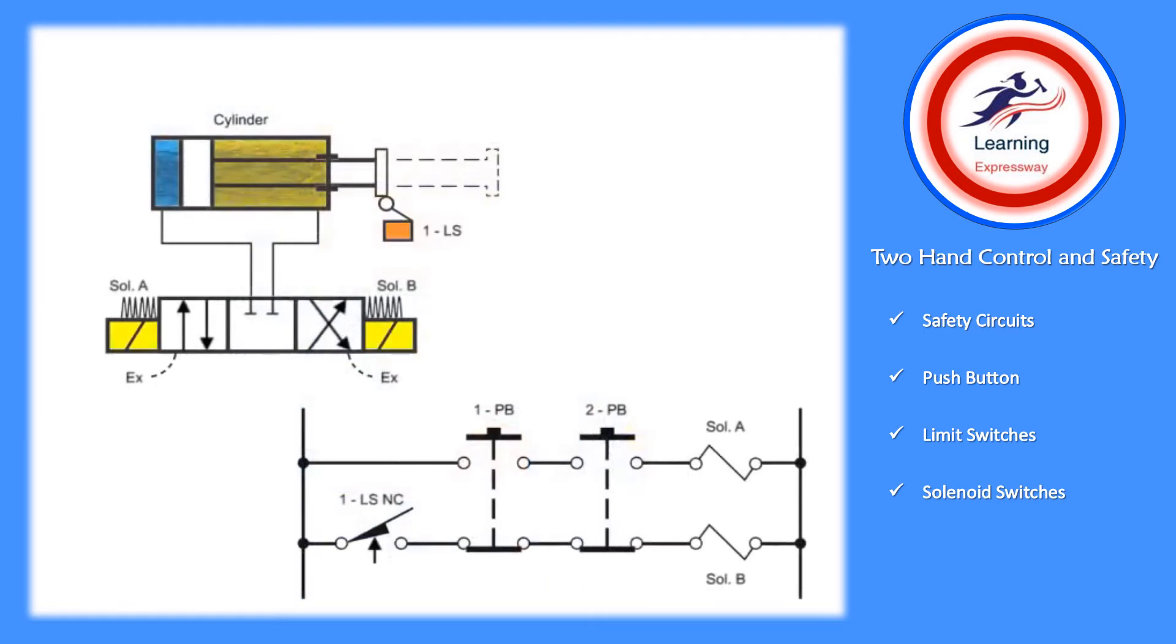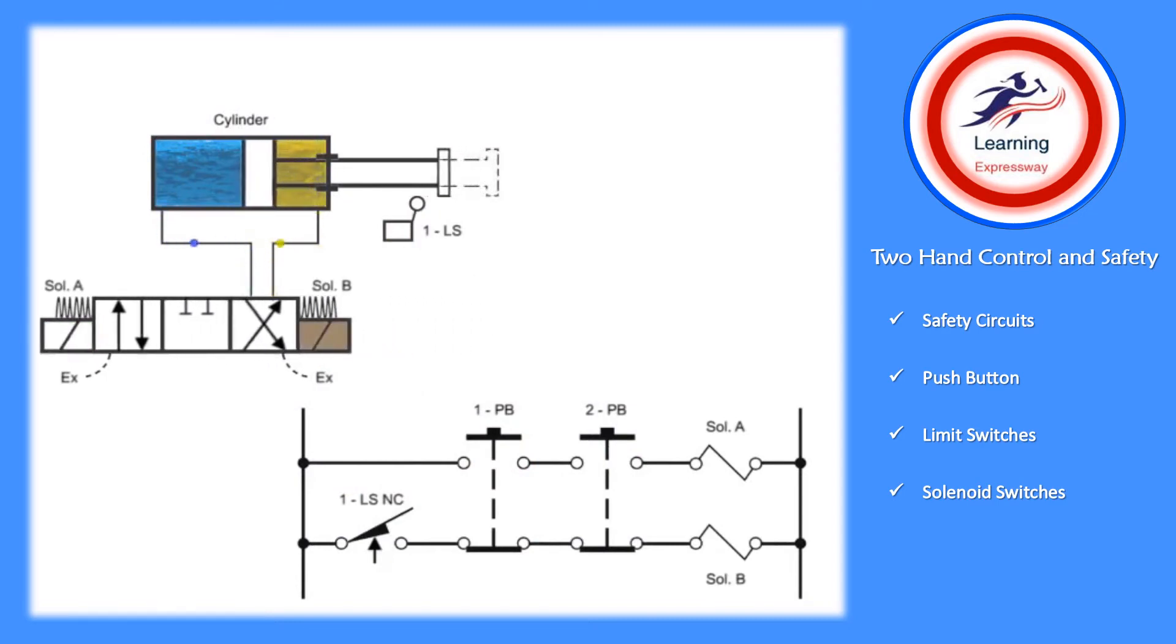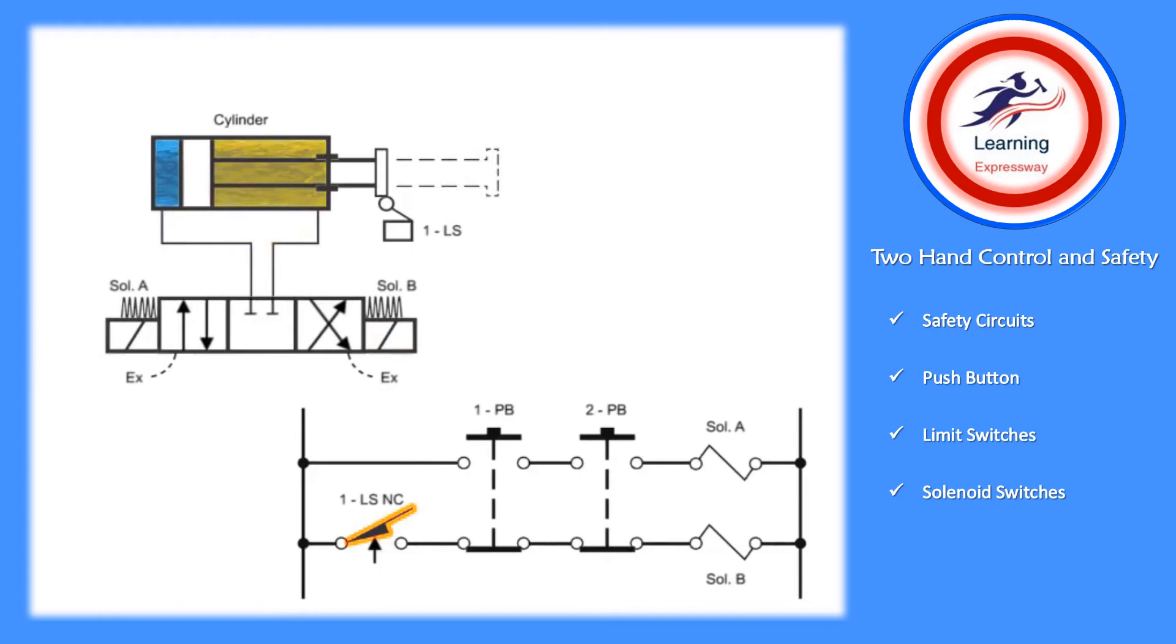In this circuit, a double-solenoid, three-position valve is connected to a cylinder which actuates a limit switch. The valve's solenoids are operated by two buttons, each one having a normally open and normally closed set of contacts. They are wired with both their normally open and normally closed contacts in series.